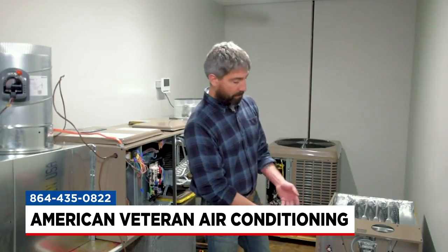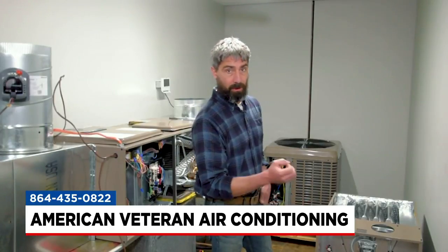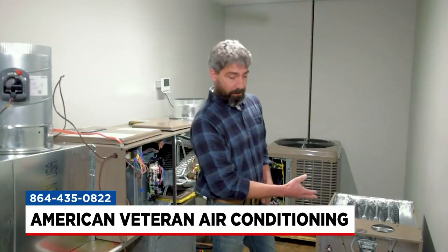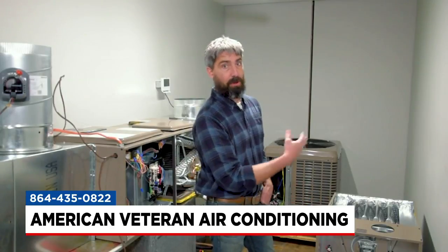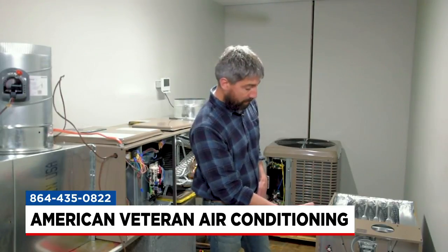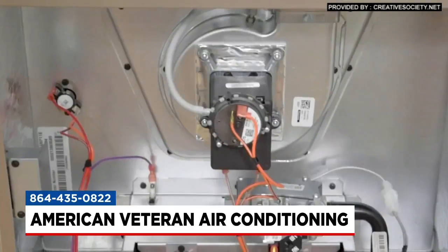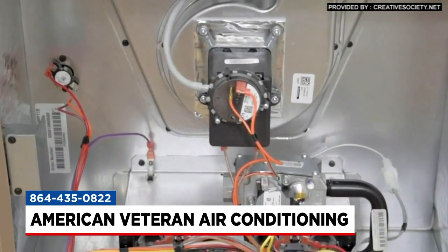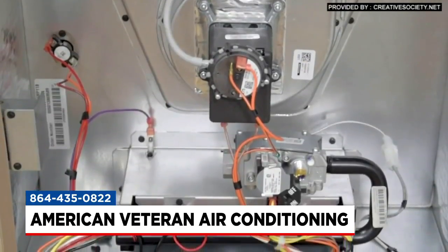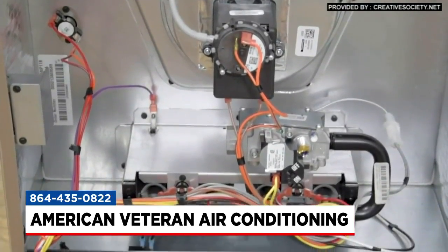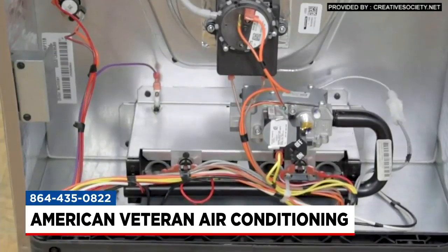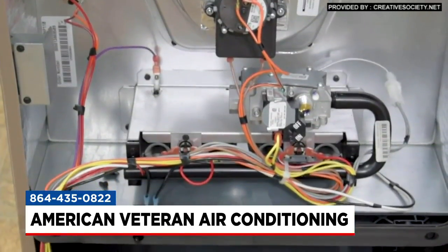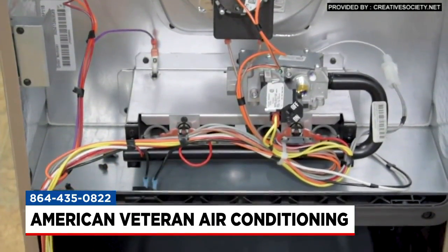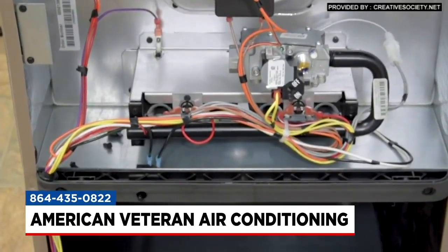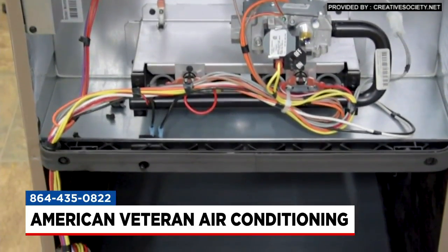Beyond that, we'll make sure the gas pressures are set right, we're getting the proper amount of gas firing into the system, and getting the proper amount of combustion air going into the system. Check all the safety switches. I come across a lot of furnaces and find out that somebody went out there at some point, the furnace wasn't working, and they just jumped out the safety switch. Well, that safety's there for a reason, if it was tripping for a reason.